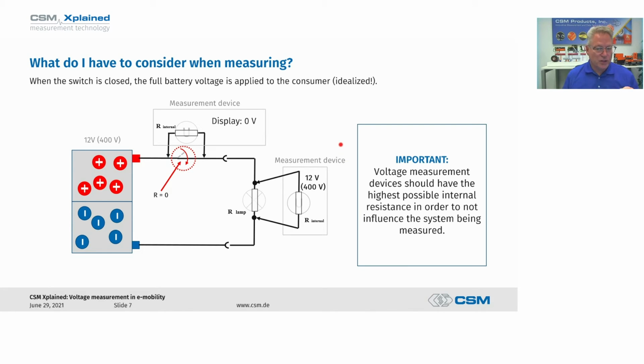Voltage measurement devices should have a really high internal resistance. This is required because current always takes the path of least resistance, so we want the resistance in the voltage measuring devices to be as high as possible. You want to make sure you don't have any effect on the system being measured. That keeps you from having incorrect measurements, or not knowing exactly where your thermal loads are going to happen, being cognizant of the whole system and knowing that your device has the least effect on your measurement.